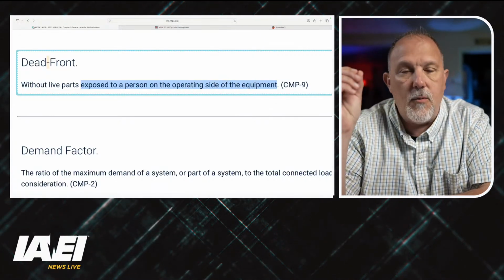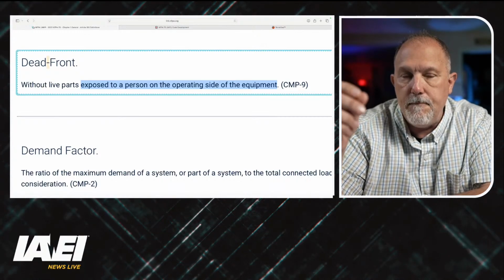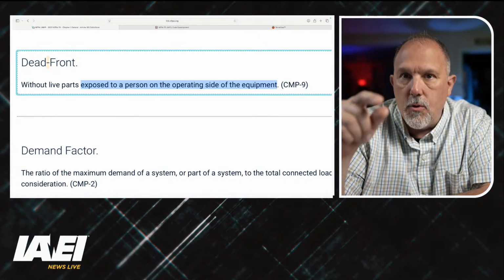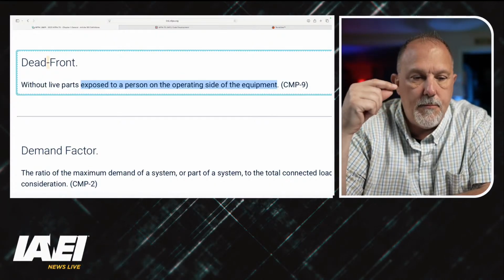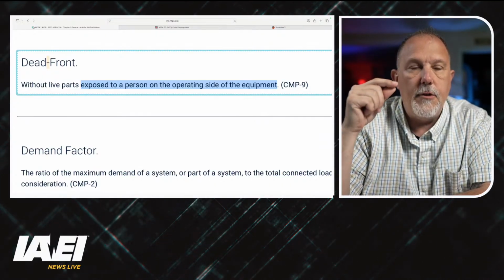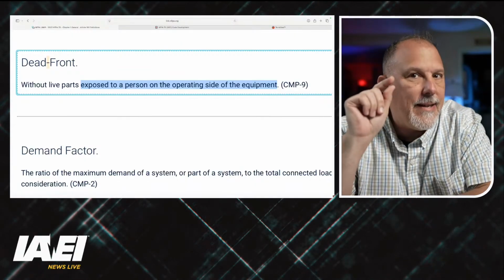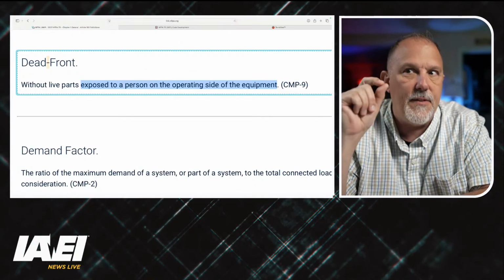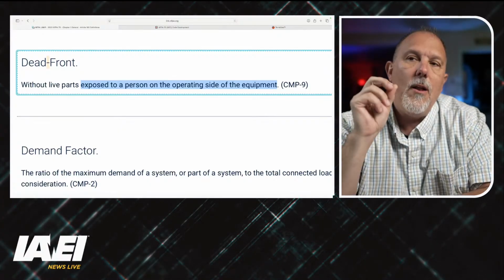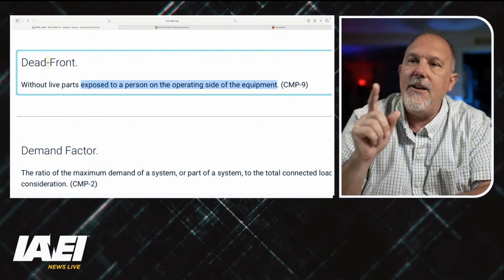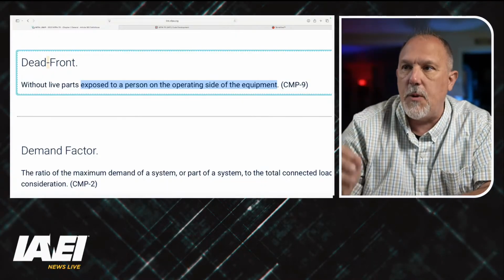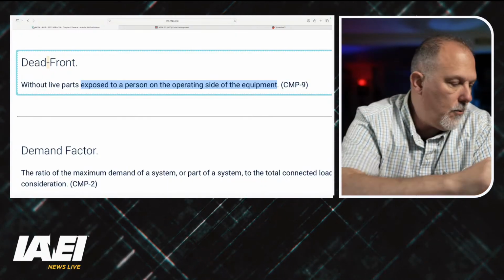Now, we can have a debate on what we mean by operating side of the equipment. Your typical panel boards employ those big metal fronts, but that doesn't mean that when I say dead front, that's what you need. All I need is to make sure that I don't have live parts exposed to a person. So if I had an enclosure where everything inside was finger safe - IP20, I think is what it's called.